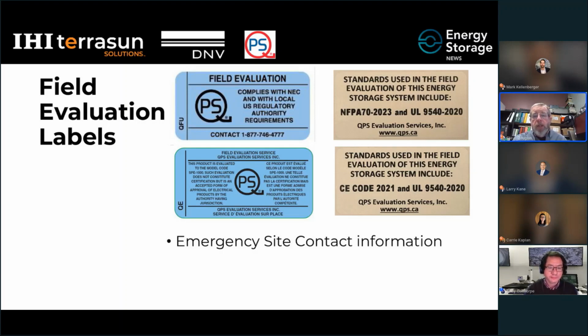The label on the right at the bottom also includes the year of the code and the year of the standard that was used for that energy storage system. This just avoids additional questions and speeds up the process on site when the authority having jurisdiction inspector attends the site and looks at the installation.